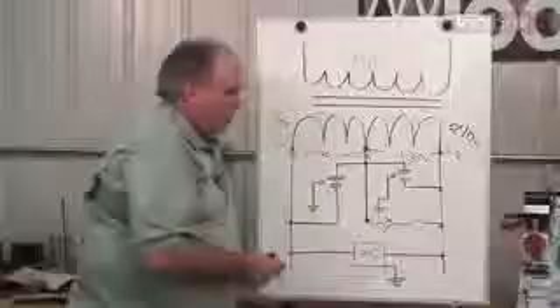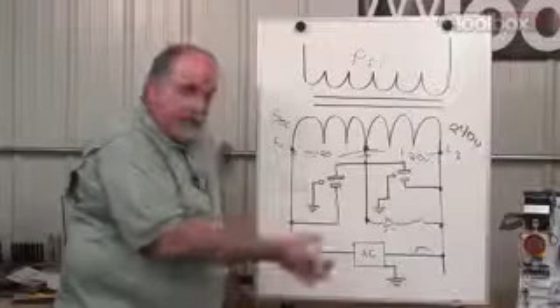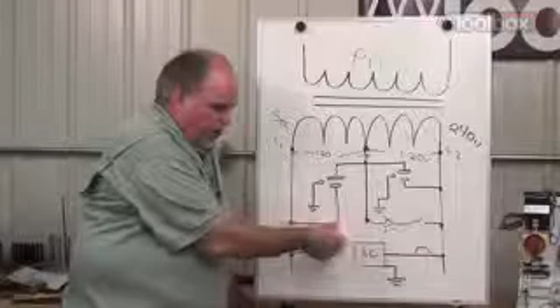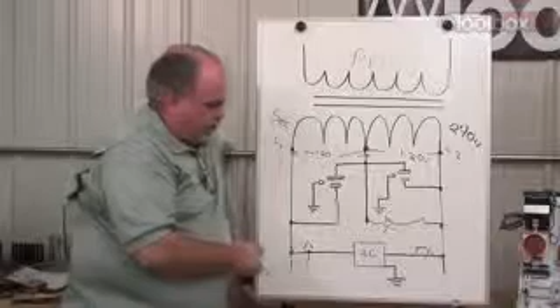Your double pole circuit breakers - the reason we use double pole circuit breakers is because there are two hot wires feeding it, and that's a circuit breaker symbol, not a very good one. The double pole breakers that feed your air conditioner have two poles, two sides to it, because L1 and L2 are both feeding that circuit breaker. If there's a problem with your air conditioner, you have to break both sides of that circuit to properly shut it off, and current on either one of those will do that.